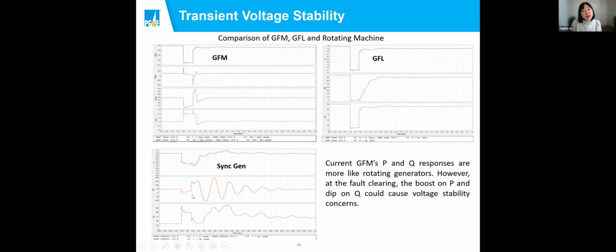And also when the fault is cleared, because of the really high boost on the real power, the acceleration causes the real power to go up a lot. The reactive power of the generation also goes down a little bit and then oscillates along with the real power. Although the grid forming inverter doesn't provide this kind of oscillation, it's very similar in PQ response upon fault clearing because of how it's designed, the nature of its control.